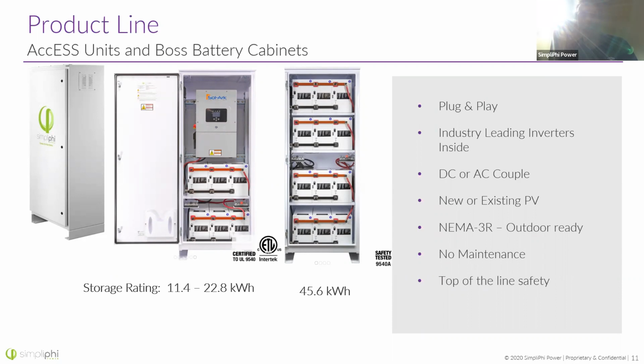And the other nice thing about this battery cabinet is that it does offer you a little bit of temperature control as well. It can be insulated. It can come with integrated heating pads for cold weather solutions if you want that. That is a special order, but we can build heating pads into the units that are controlled directly from the BMS of the battery. It's NEMA 3R rated, ready to go indoors or outdoors. Essentially no maintenance on these lithium systems, which is what makes them so nice.